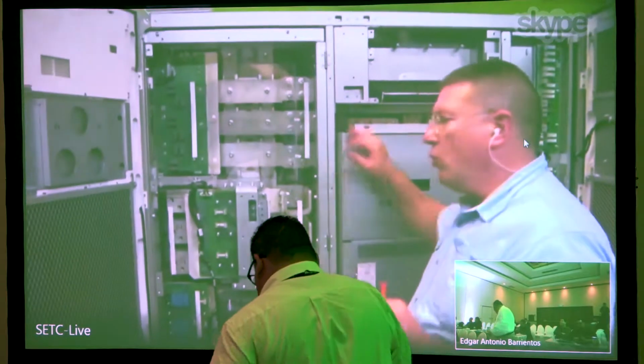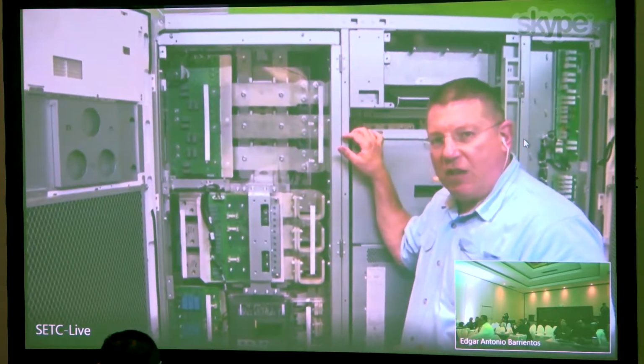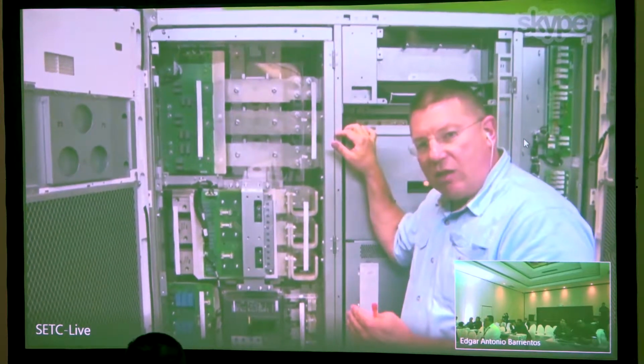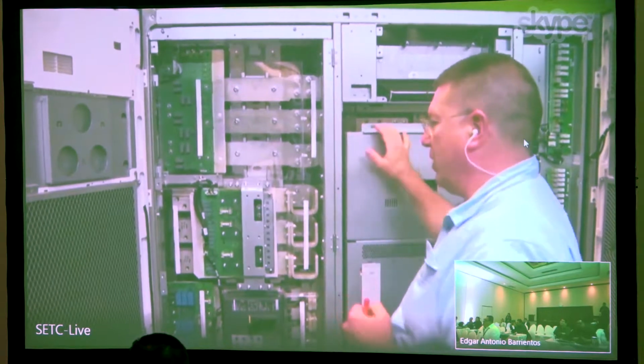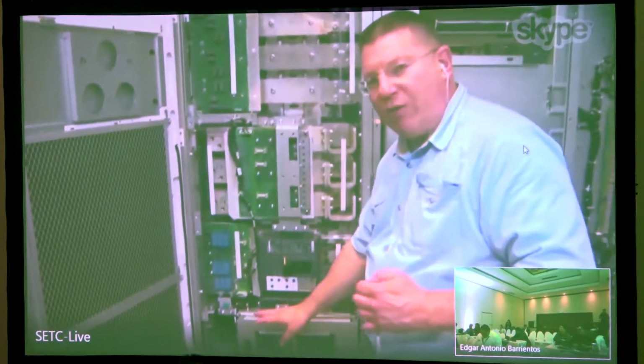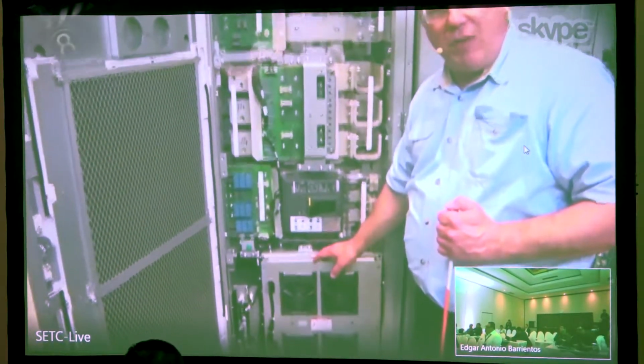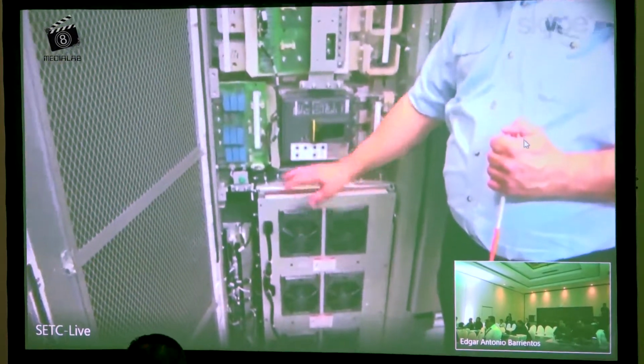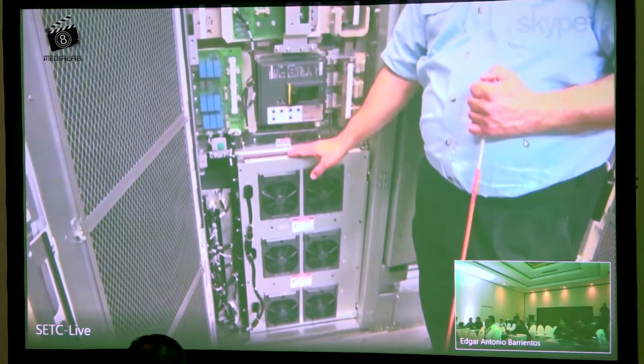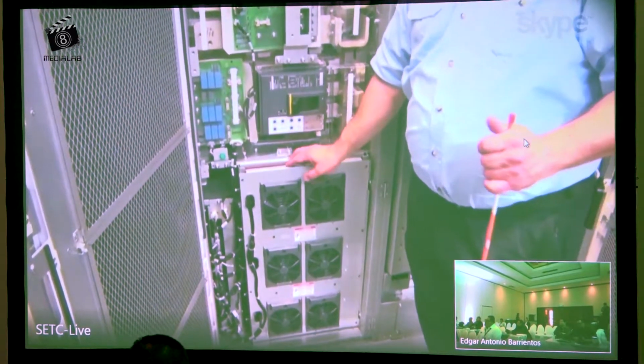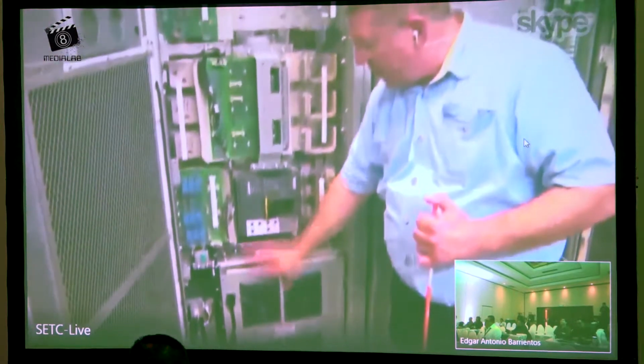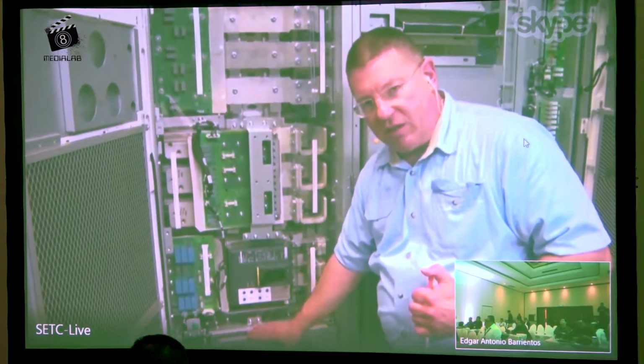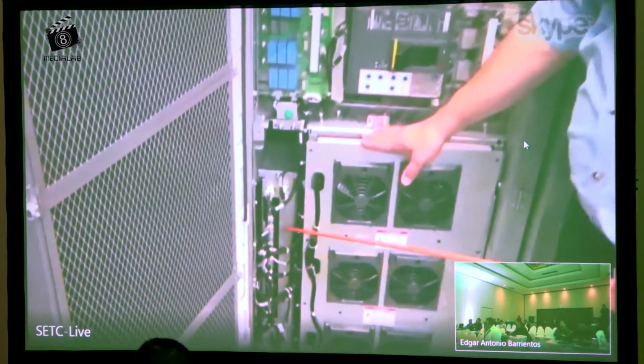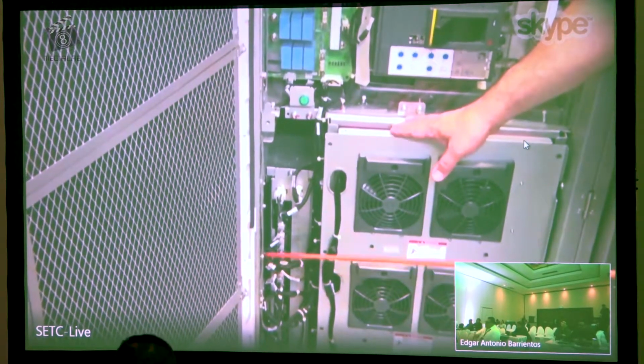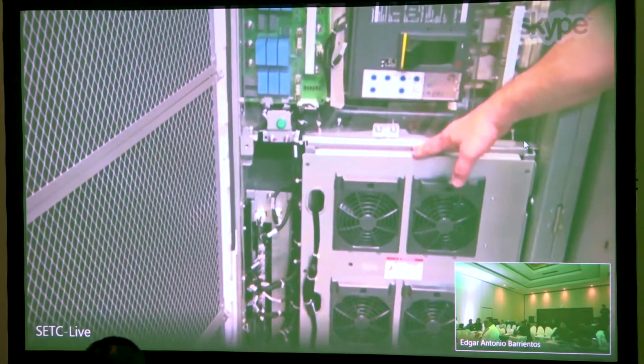We've focused primarily on a 1,000 kilowatt and a 1,500 kilowatt input-output cabinet. The 1,000 kW IOC is roughly the same size as this 750. Working from the left side: at the bottom is the static bypass switch. I've removed a lot of the dead fronts here so we can see the components — on the live unit these won't be accessible since it's live and we need to be safe. All the way over on the left side is where our power supplies and controls are for the static bypass, all tied to the main controller, which I'll talk about in a minute.